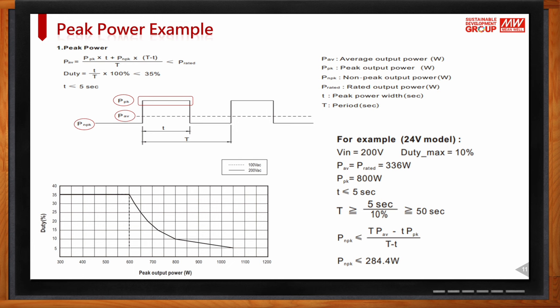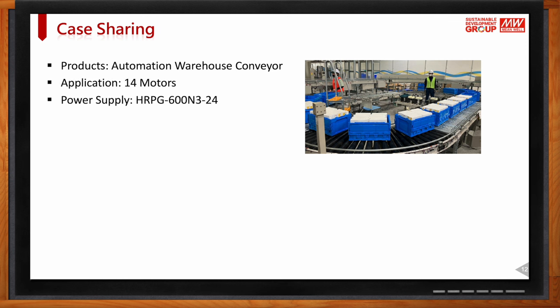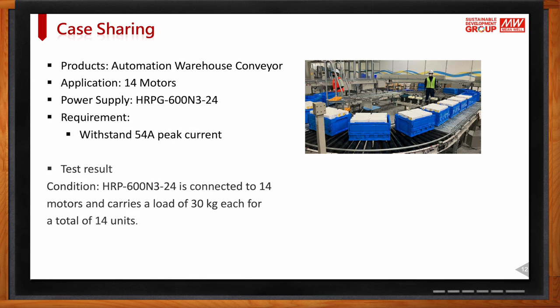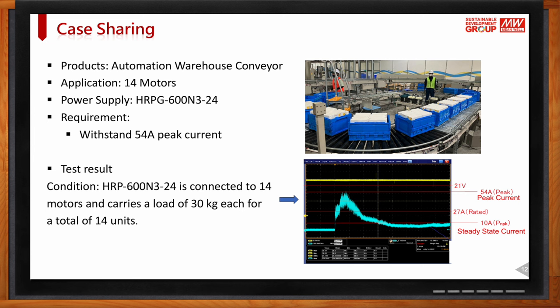What would a typical application look like? A customer has an automation warehouse conveyor with 14 motors and peak current of 55A. From the oscilloscope, the highest current required is 54A at 24V motor voltage. We suggested the customer use the HRP-600-N3-24. This power supply can handle all 14 motors, and as you can see from the graph, no voltage drop occurred because this power supply handles the peak power demand at startup for all 14 motors.